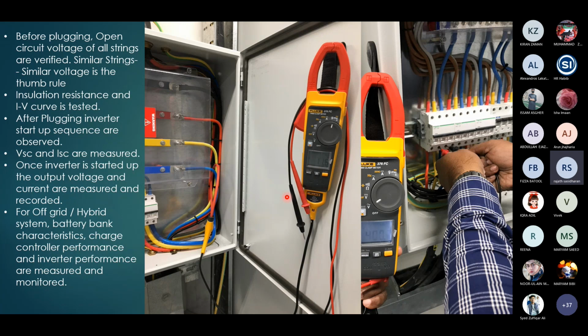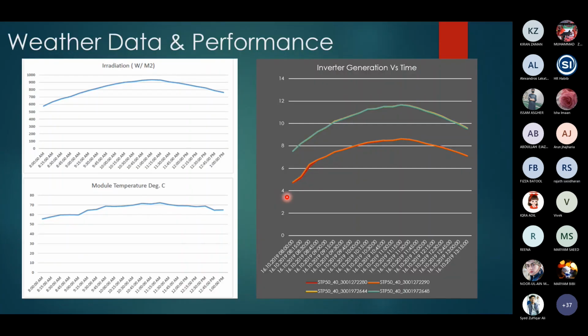After plugging in the inverter, we observe the startup and the process in which the inverter wakes from sleep. During that process, it checks the different voltage levels at the terminals, and then it is ready to convert that energy into AC. It gives you a signal, okay, I'm ready to pump AC. So then we switch on the AC also. Once it is done, the inversion starts and we take the reading on both sides, what is available from the DC, what is available from the AC side.